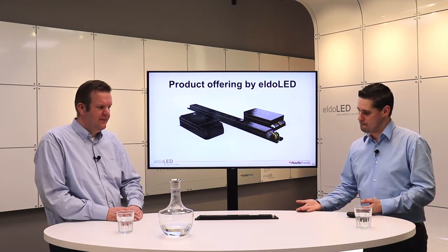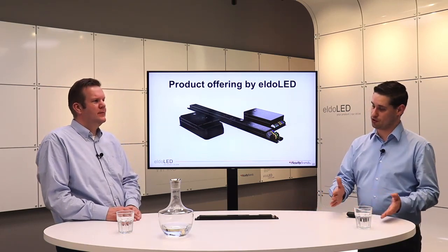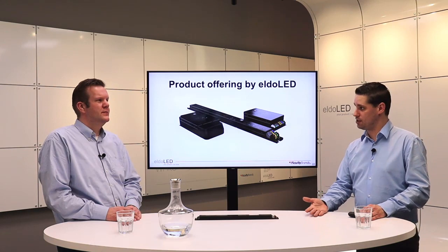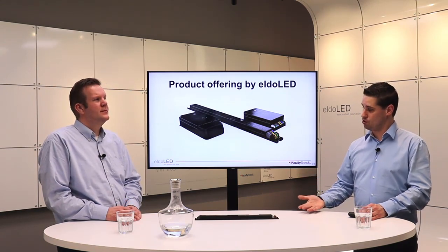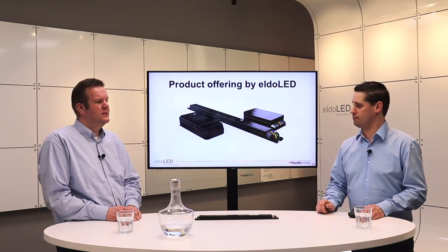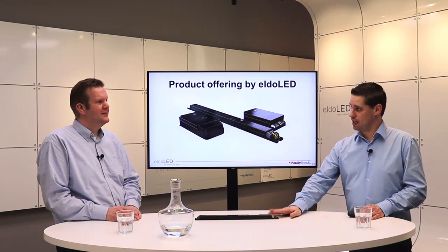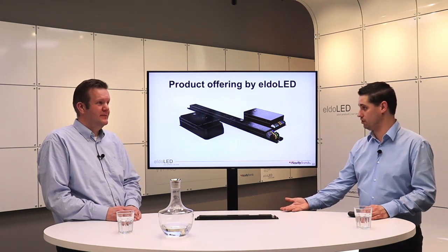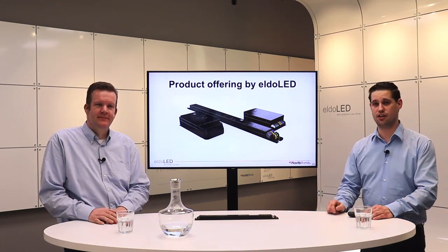Got it. Yeah. But there are multiple ways to avoid overloading the product. It's from connecting the right amount of LEDs, but if you connect too many LEDs, you can also use some settings inside the driver to scale the power in such a way that you're never exceeding that 50 watt of the driver. Total flexibility. Exactly. And all that information you can find in our design-in guide, which is available on our website. Yeah. It might be interesting to look into that design guide as well.